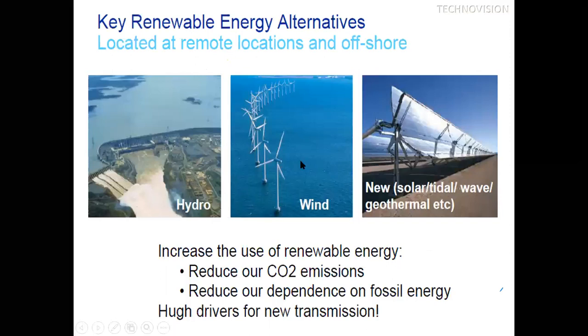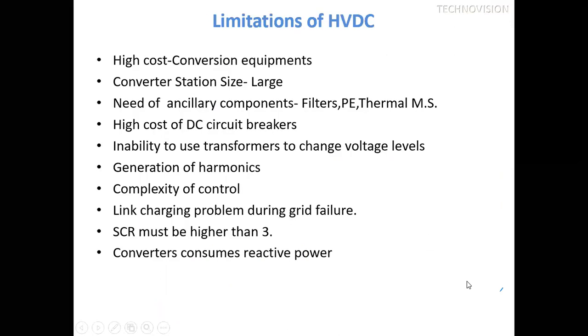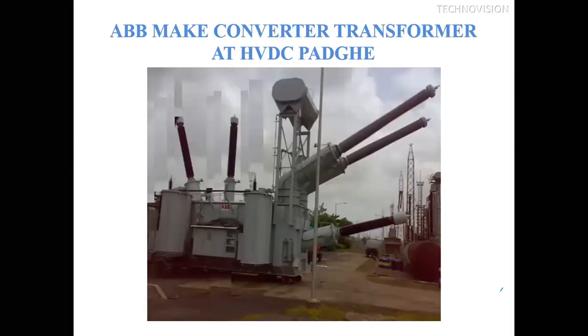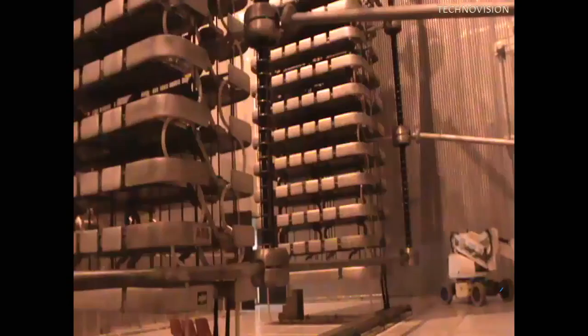Hydro, wind, thermal, solar, all the systems you can connect with voltage source converter based technology. Now the limitations: the cost of HVDC is more, converter station size is large, then there are filters, power electronic devices, a thermal management system is needed, high cost of DC breakers which we use in the neutral path, then inability to use transformers to change voltage level, generation of harmonics, complexity of control. These are some of the limitations, but with the help of new technology like voltage source converter, all these limitations have been overcome. This is the converter transformer of HVDC. This is the smoothing reactor. This is the thyristor valve.